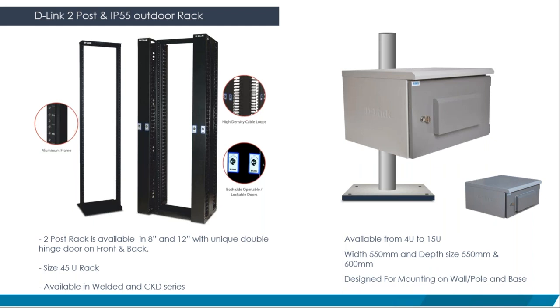These are IP55 outdoor racks. We always recommend using IP54 or IP55 outdoor racks for installation of the industrial switches, because of proper ventilation. If we go with IP65 or IP66, the outside temperature may be 50 degrees, and the inside temperature of the rack may go 10 or 15 degrees higher.